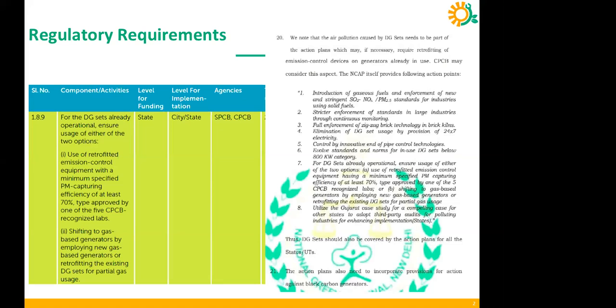It all started 2 years back when the Ministry of Environment and Forest came up with the National Clean Air Program in 2018, which addressed diesel generators as one subject. They identified that diesel generators currently contribute up to 18% of air pollution emissions, and wanted to bring that down significantly. So they came up with two advisory options: use a retrofit emission control equipment with a minimum specified PM capturing efficiency of at least 70%, or shift to a gas-based generator.